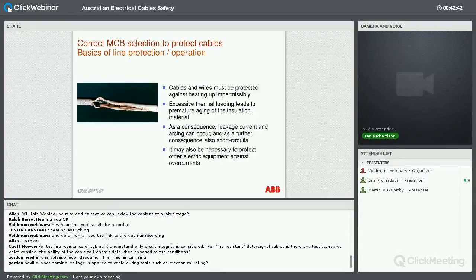As a basic rule, when we put a circuit breaker in a lot of power distribution situations, we're actually protecting the cable which is leading to that load. We're not necessarily protecting the load, although that does come into it. From a thermal point of view, we would be rating the cable in accordance with the characteristics of the cable that we're trying to protect. Often it's looked at in the other way. We have a certain protective device, we choose the cable which is appropriate to that protective device.